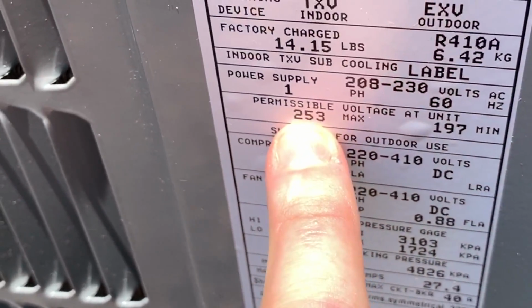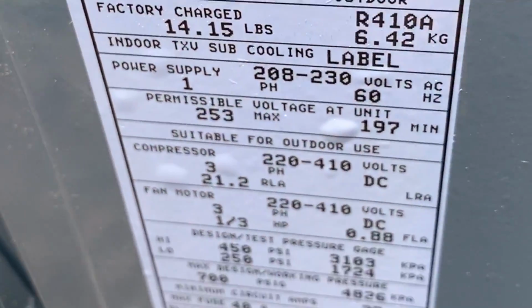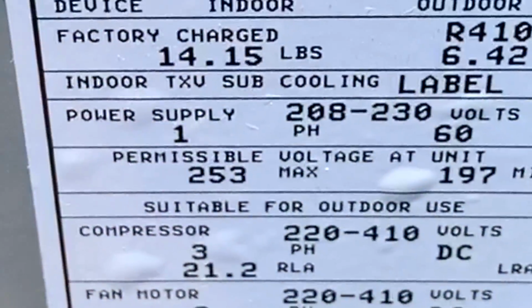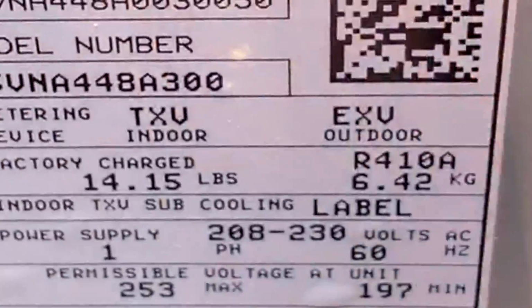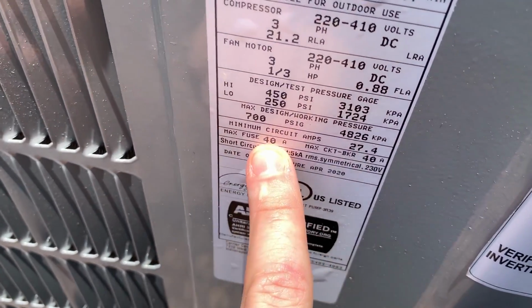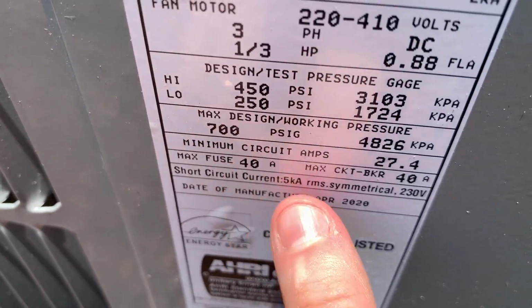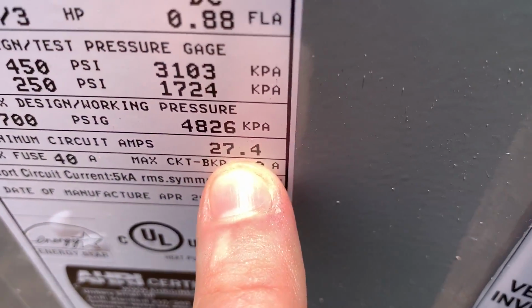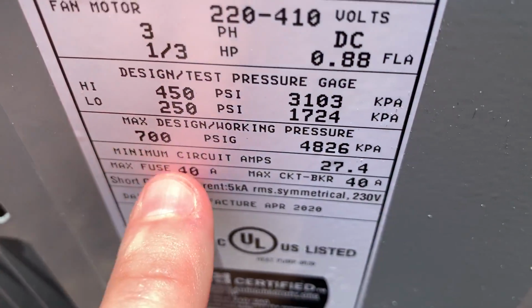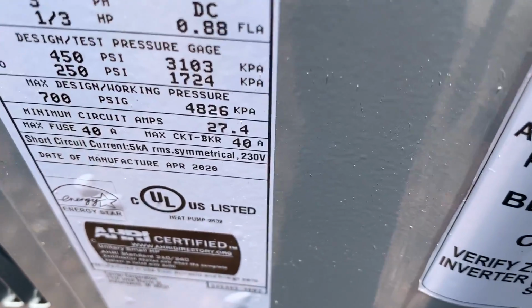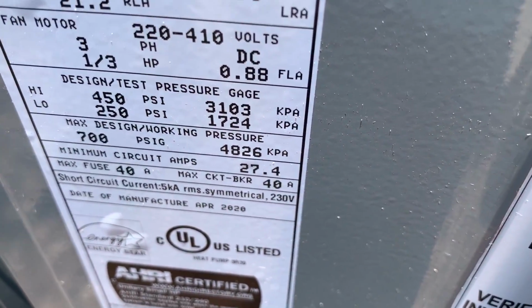Big part of the testing is to make sure that we're not exceeding our maximum voltage in our market, which is another reason why we put the ICM 493, because in our experience, exceeding the maximum voltage on these can result in failure. Maximum fuse 40, so we're good to go. And on this we could actually put a number 10 wire because that is the minimum circuit ampacity. If you don't believe me, look it up before arguing.